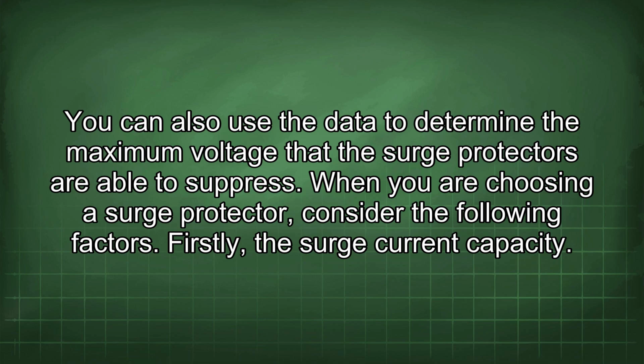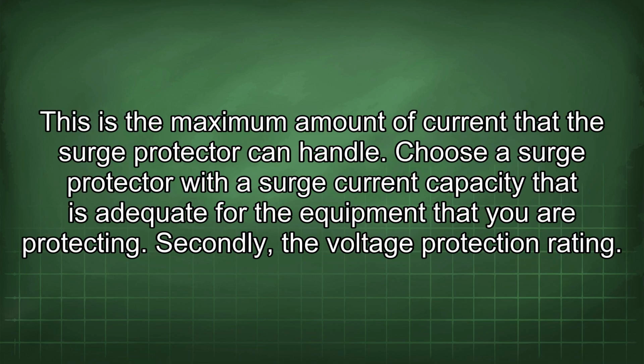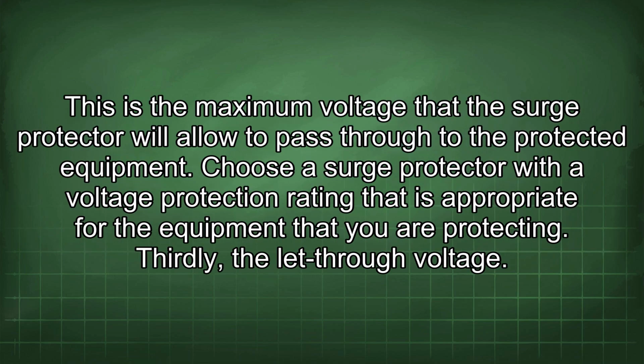When you are choosing a surge protector, consider the following factors. Firstly, the surge current capacity. This is the maximum amount of current that the surge protector can handle. Choose a surge protector with a surge current capacity that is adequate for the equipment that you are protecting. Secondly, the voltage protection rating. This is the maximum voltage that the surge protector will allow to pass through to the protected equipment. Choose a surge protector with a voltage protection rating that is appropriate for the equipment that you are protecting.